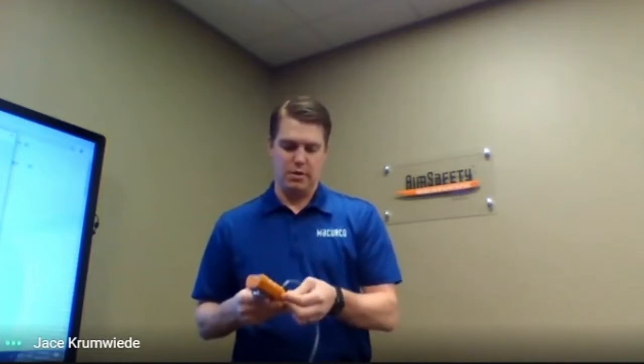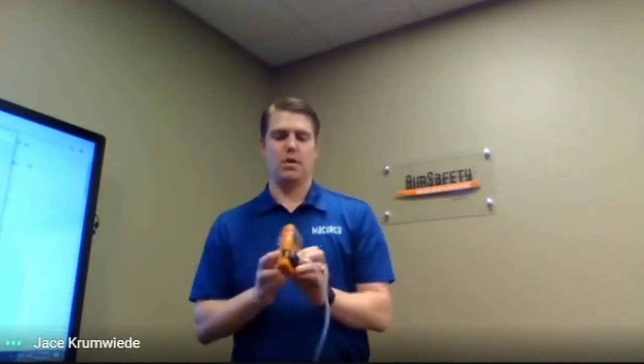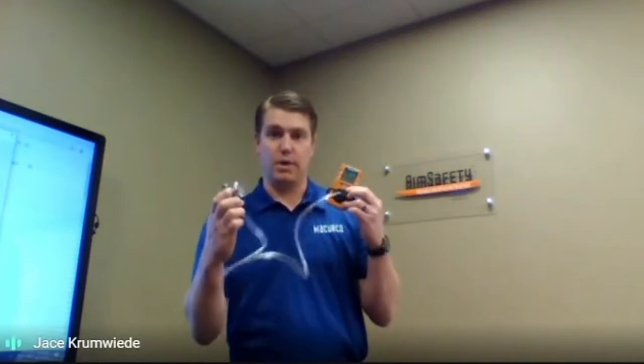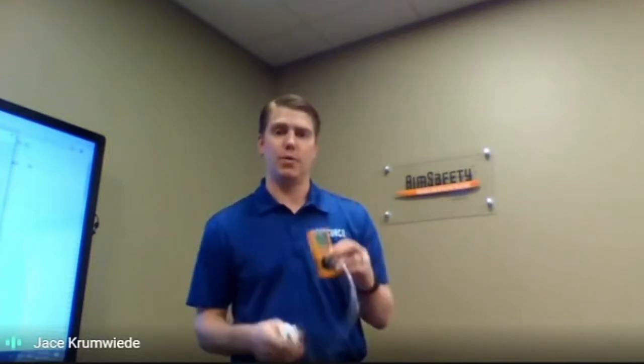Various screens and alarm levels that you'll see in here. This calibration hood that I showed you previously actually just snaps right into the front of the unit. So if you're going to do a manual calibration, you got it right there, and then that's where you have your bottle of gas and you're applying it into it. Pretty straightforward, again, very rugged, designed for explosion-proof environments, and very rugged as well, so it does have the IP67 rating on that.